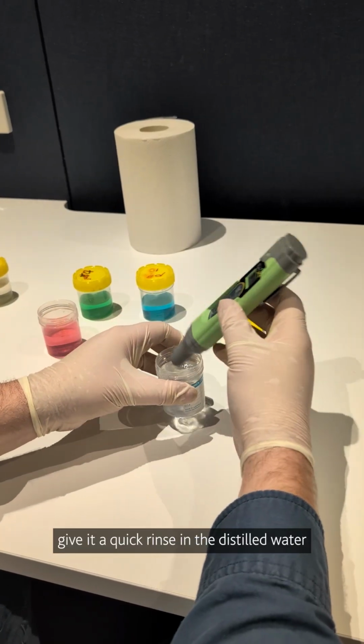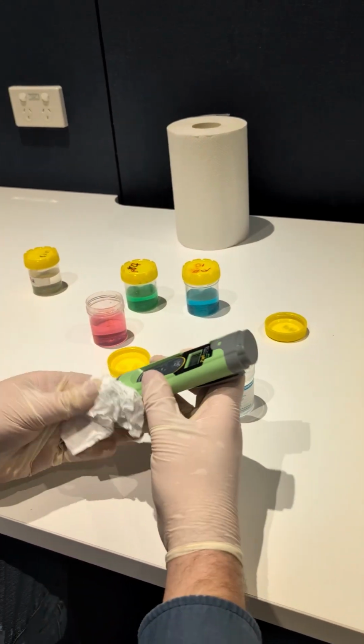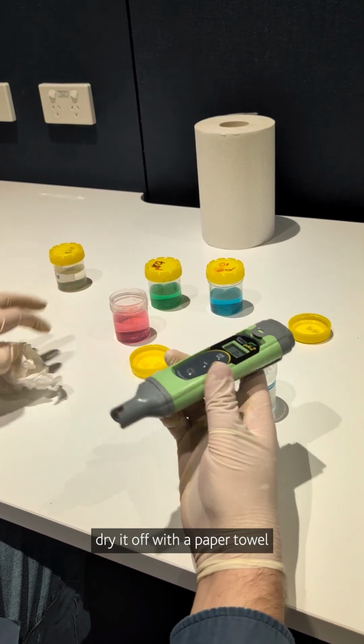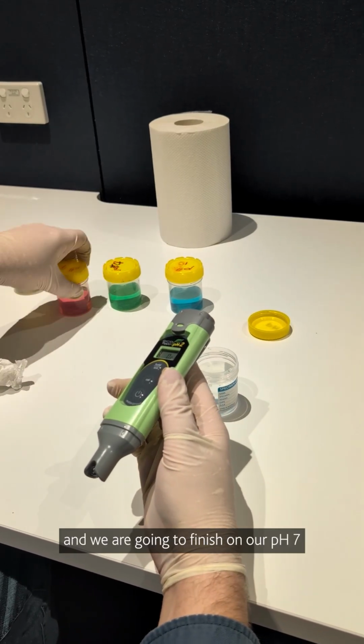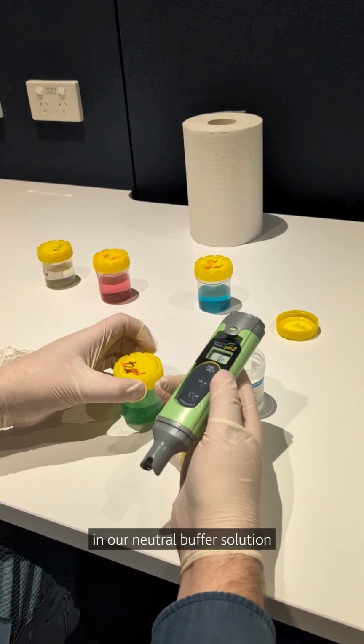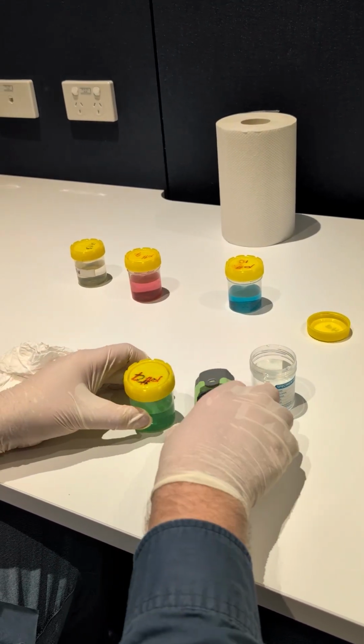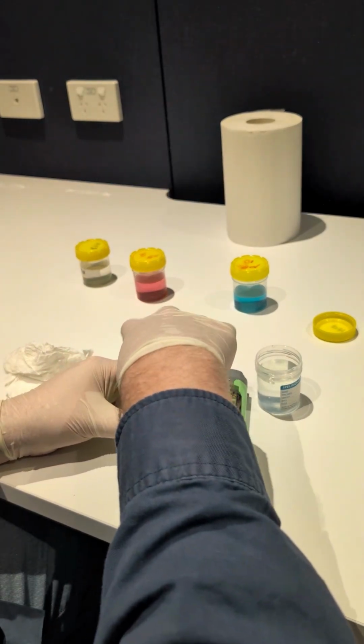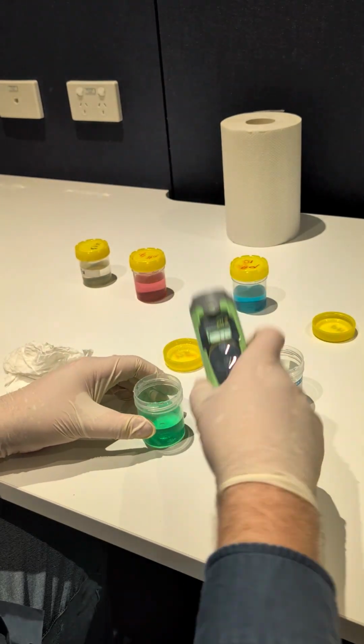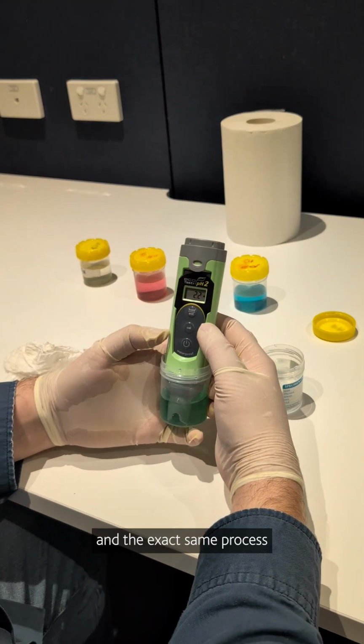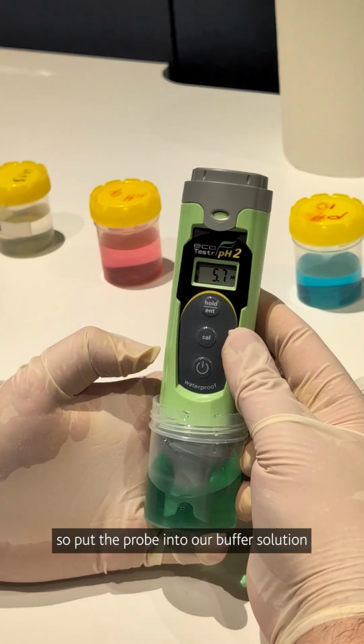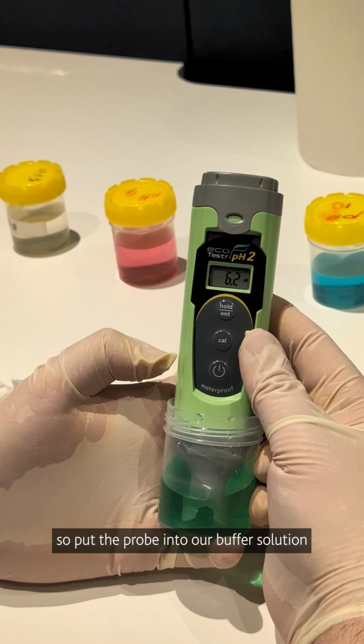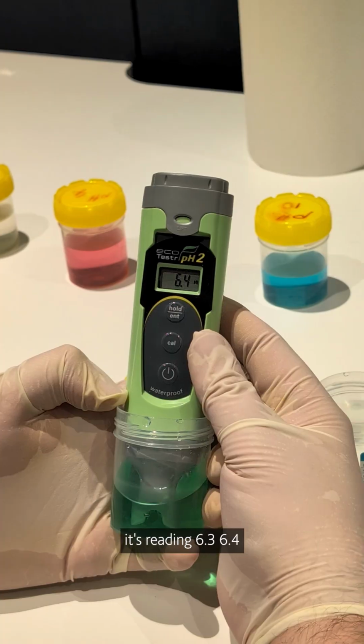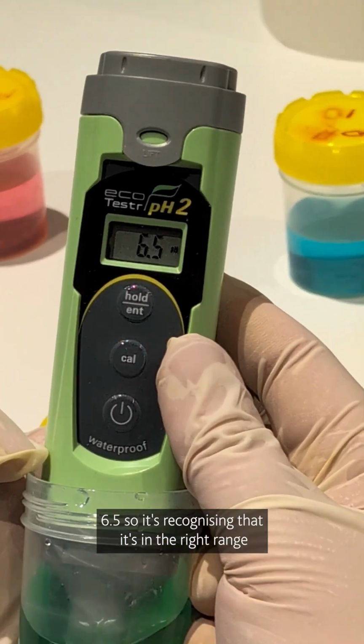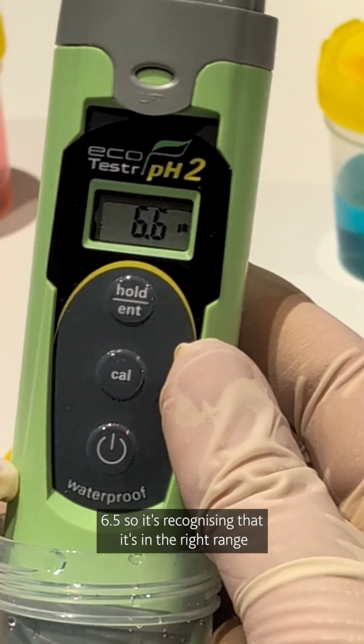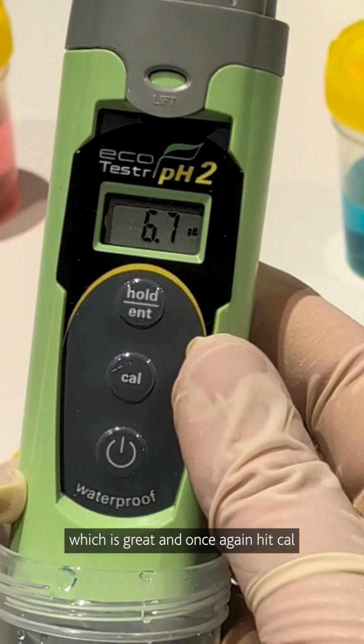Give it a quick rinse in the distilled water. Dry it off with a paper towel. And we're going to finish on our pH 7, our neutral buffer solution. And it's the exact same process. So put the probe into our buffer solution. It is reading 6.3, 6.4, 6.5. So it's recognizing that it's in the right range, which is great.